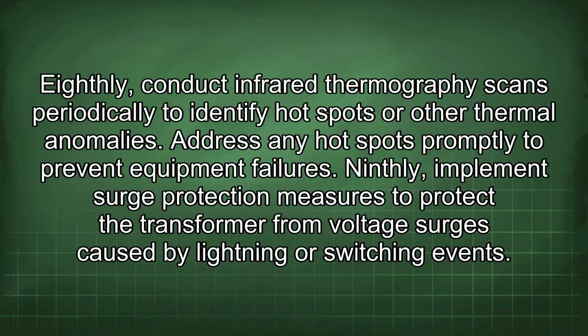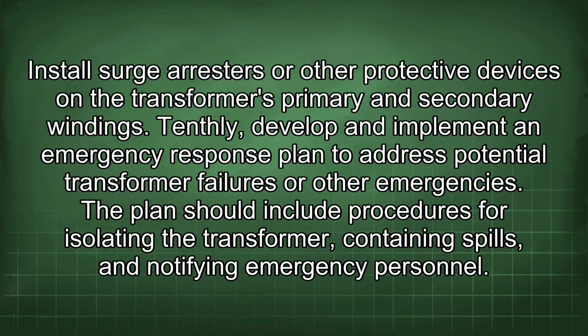Ninthly, implement surge protection measures to protect the transformer from voltage surges caused by lightning or switching events. Install surge arresters or other protective devices on the transformer's primary and secondary windings. Tenthly, develop and implement an emergency response plan to address potential transformer failures or other emergencies. The plan should include procedures for isolating the transformer, containing spills, and notifying emergency personnel.